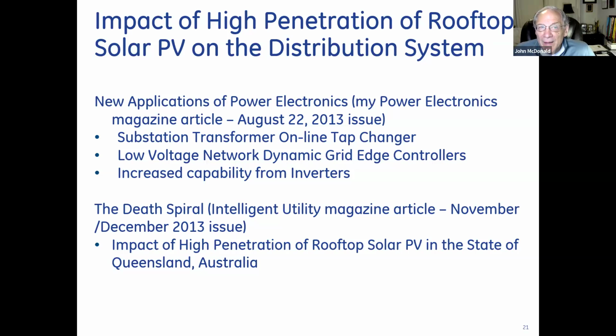We do this when there's a high penetration of rooftop solar PV on the distribution system. This is an example in San Diego, California. On one distribution feeder, many homeowners installed rooftop solar panels, in fact over 35%. This is an issue because these homes are along the Pacific Ocean, and in the morning there's humidity from the ocean that causes fog over the homes, blocking the sun. As that fog burns off, all homes begin generating at the same time, and the voltage on the feeder spikes and then oscillates.